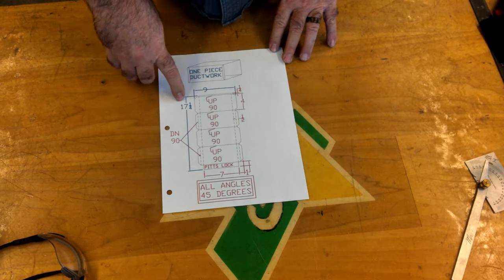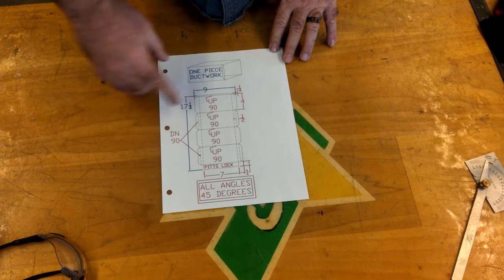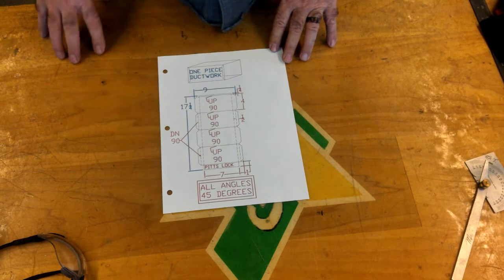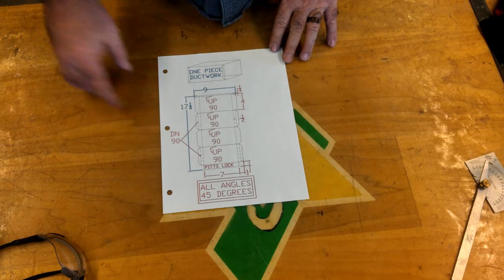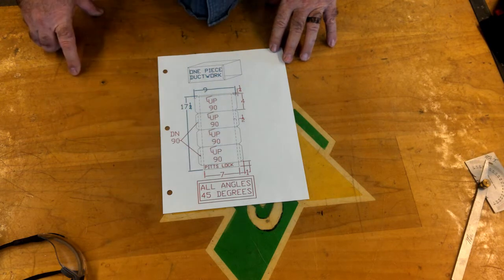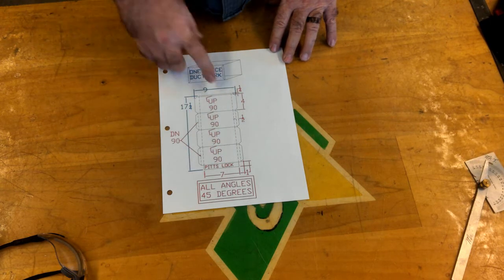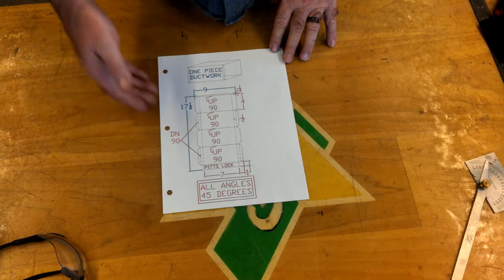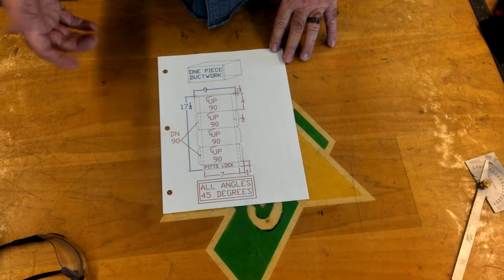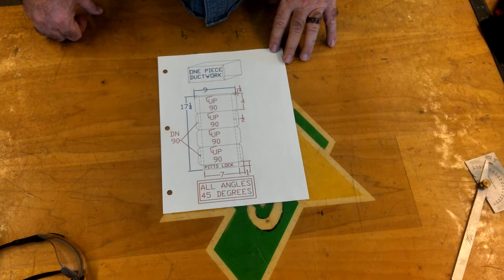Our cut size is 17 1/4 by 9. We have our 4-inch dimensions, 4 times 4 would be 16. Our Pittsburgh lock allowance is 1 inch, and our return flange is 1/4. So when we add those all up together, we get our 17 1/4 inch piece.